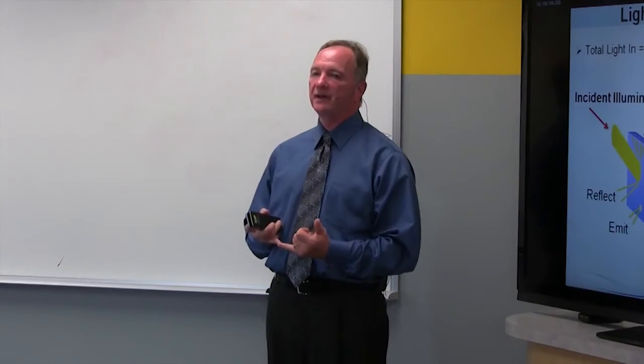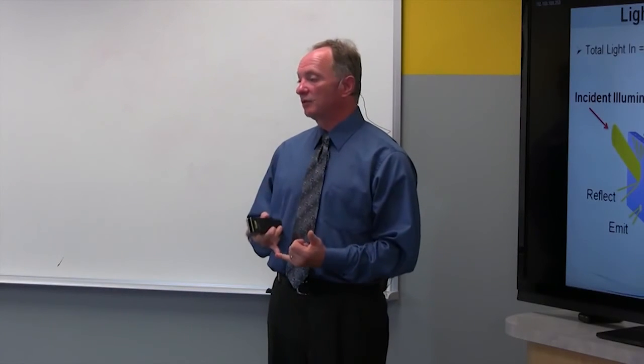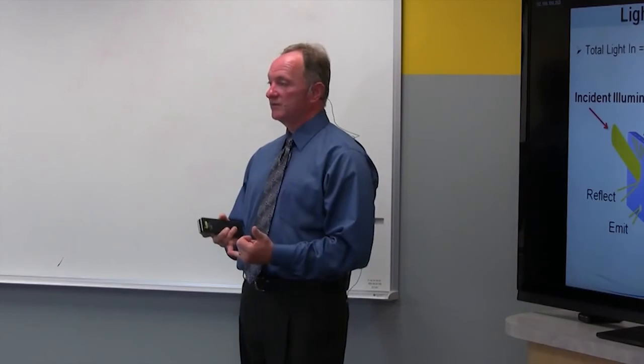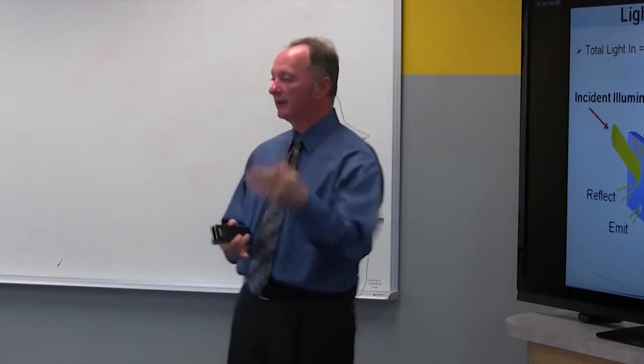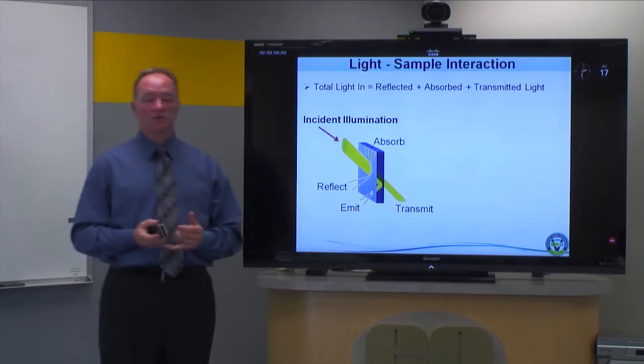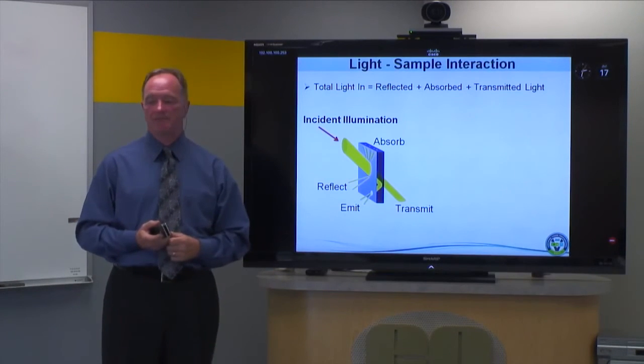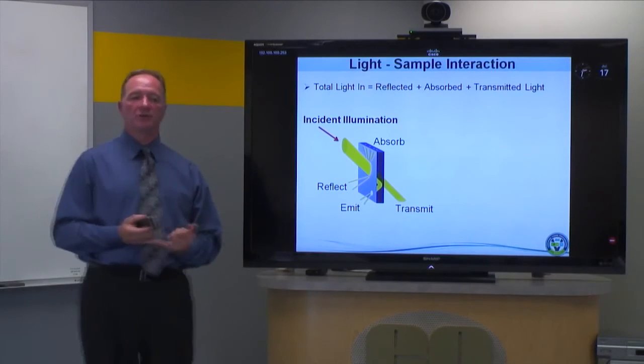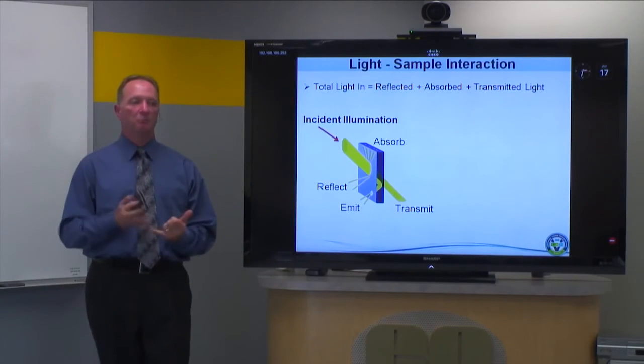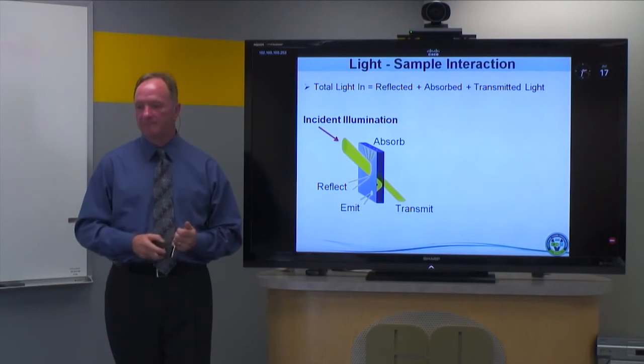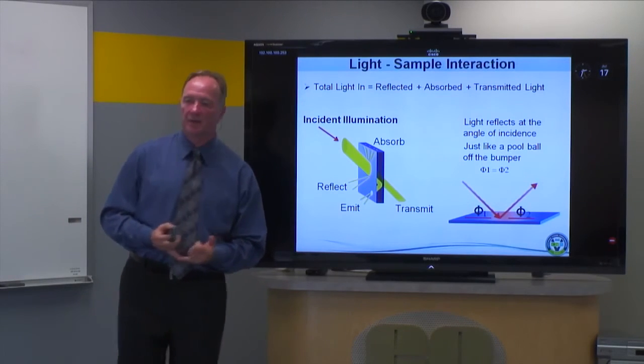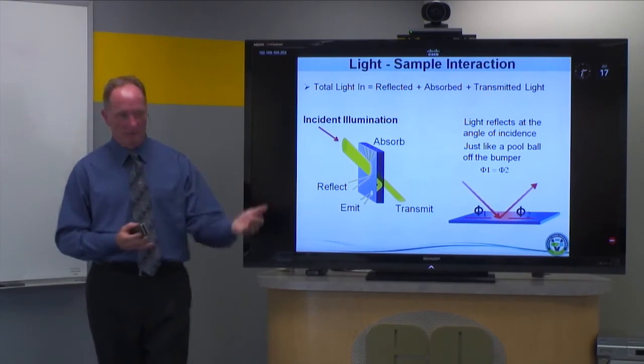When light is incident on a sample surface, you get the possibility for reflections, absorption and diffusion, transmission through the sample, or re-emission — secondary fluorescence. Many samples show a little bit of all of these, so it depends on which is most important for you and which area you can apply your lighting to for the best, most sample-appropriate solution. Remember: angle of incidence always equals the angle of reflection, and we're going to use that to our advantage when discussing bright-field versus dark-field lighting.